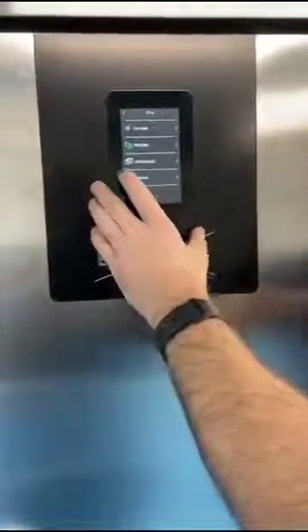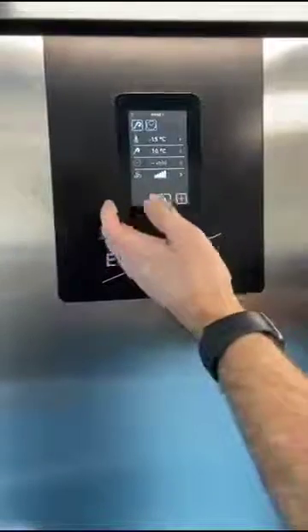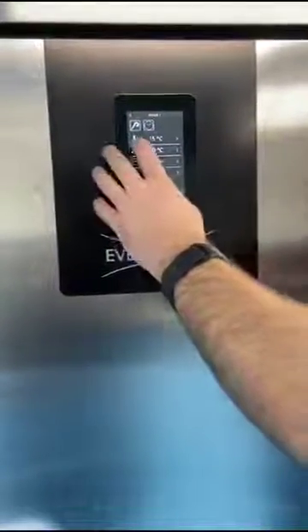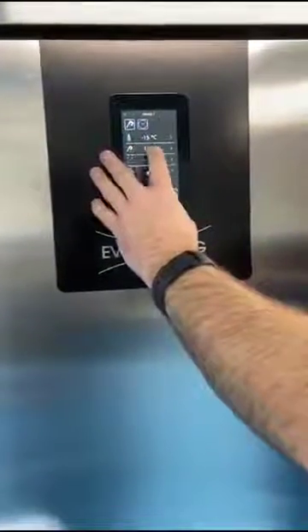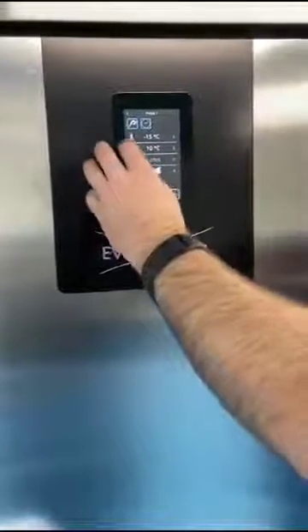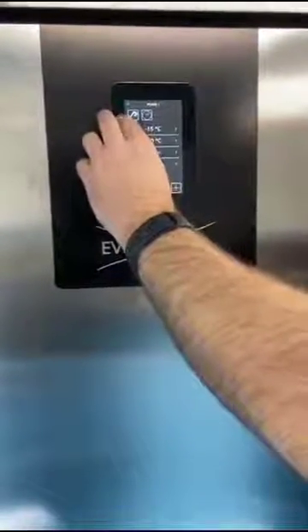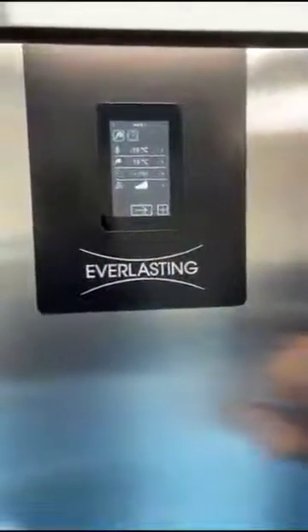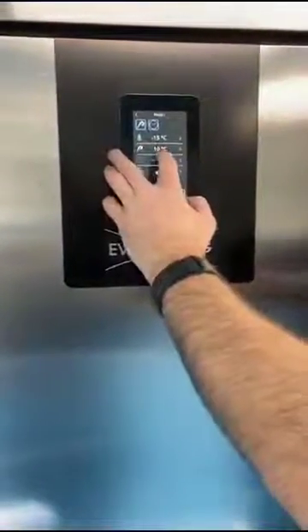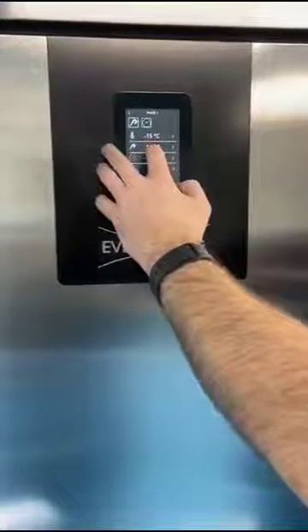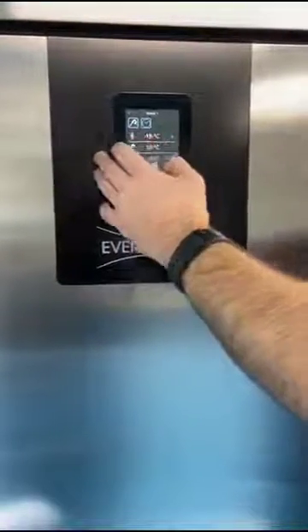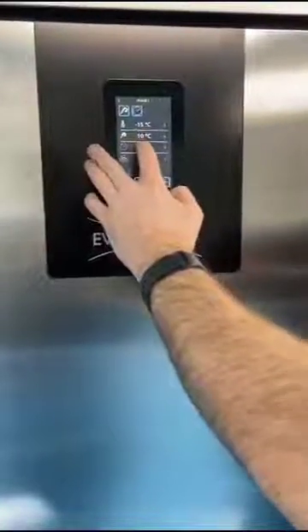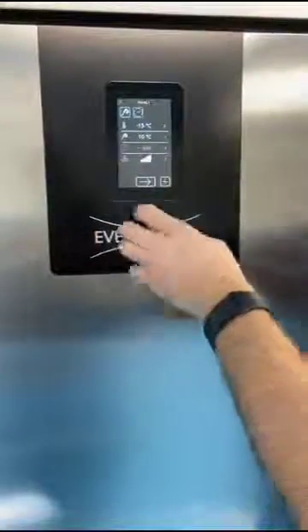So if you're doing a very simple function, you might just go into manual and quickly select the air temperature you want in there, the temperature you want to reach. Again, that's your core probe, where you put the pin into the product inside, and the core of that product is going to determine when it's reached temperature. So let's say you want to reach 10 degrees in there. The core probe will run with -15 air going into the cabinet until the product has reached 10.